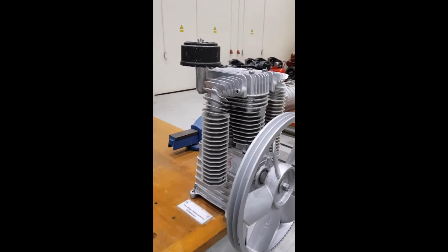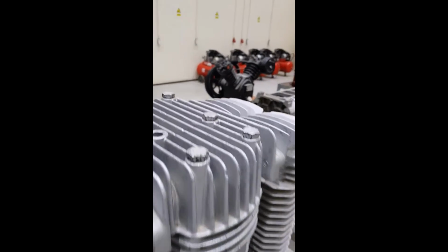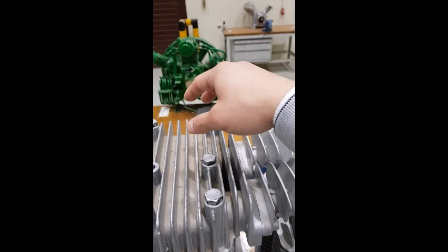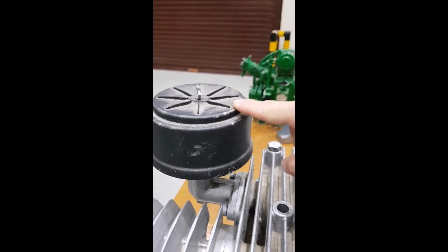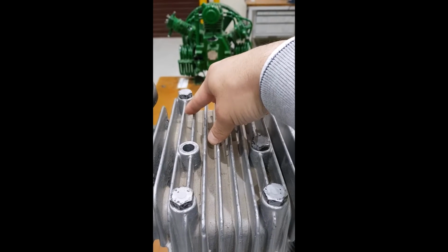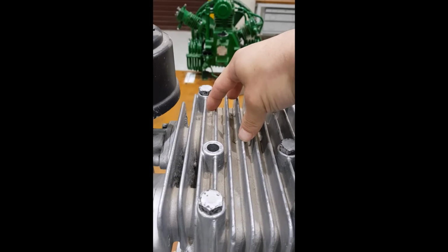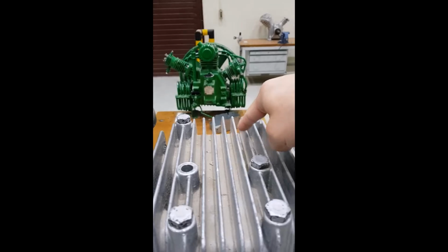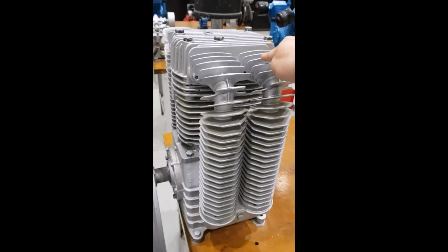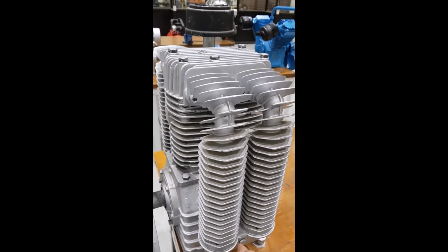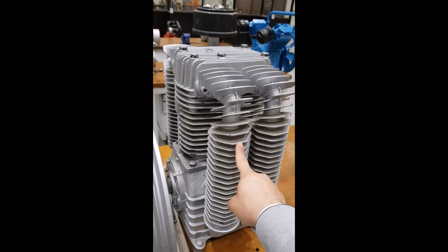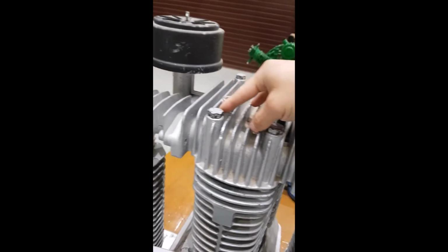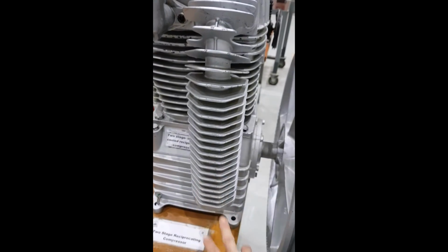This is another example of a two-stage reciprocating compressor. We have a filter over here, which means this is the area of the first stage. So here is the first stage, here is the second stage. Air enters from here through the filter to the first stage, the piston over here. After they get compressed, they move through the intercooler, which is the fin type, as we discussed before. From there they go to the second stage. From the second stage they go outside through the aftercooler. Again, it is a fin type.